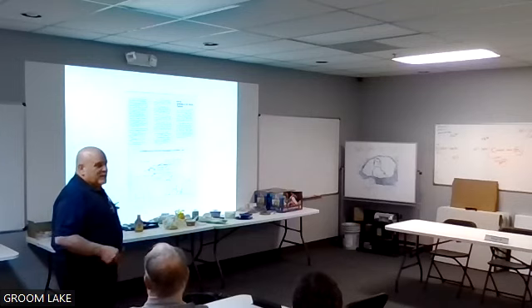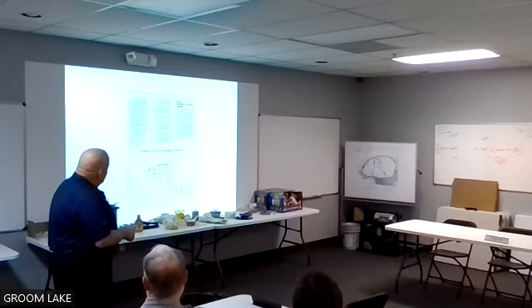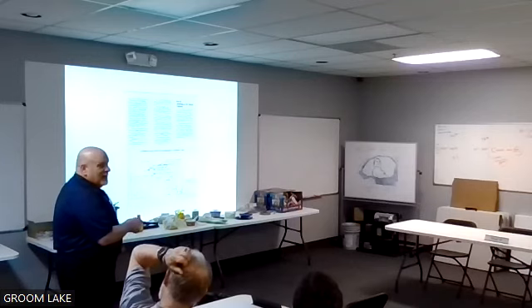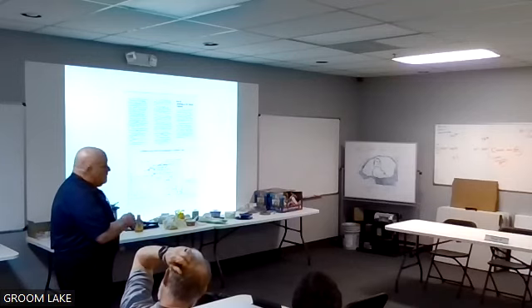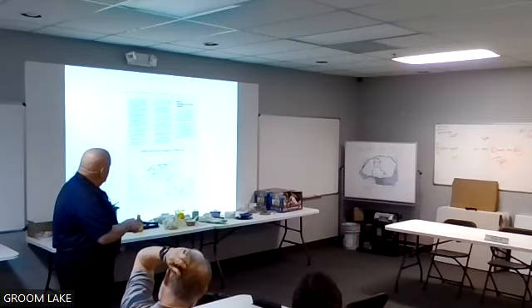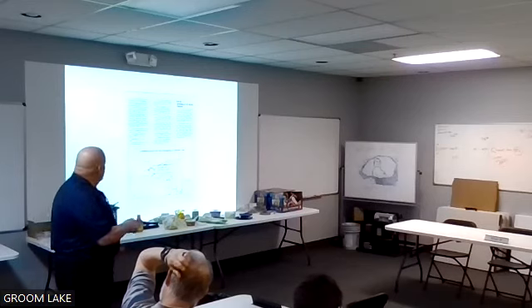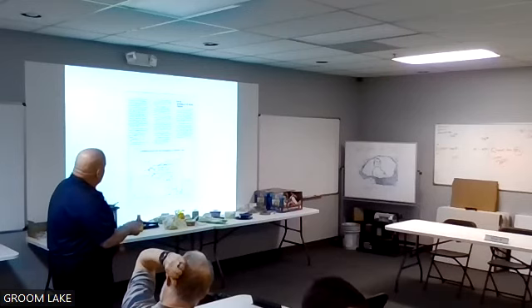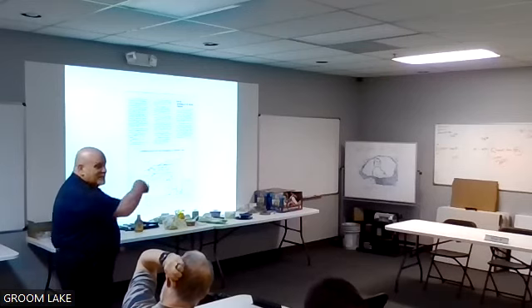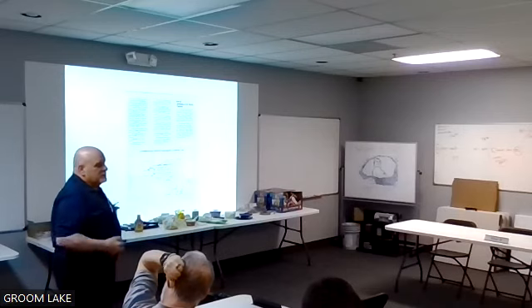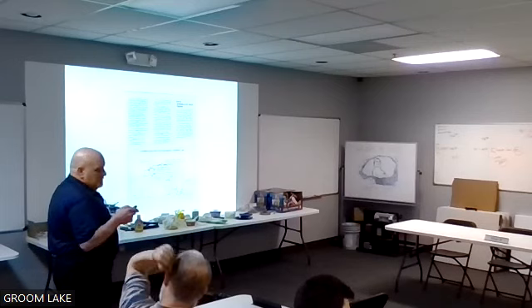You're taking up expansion space, really. So you always put this here, you put an air vent up here on this one, instead of returning it to the tank, I want it to go to atmosphere. And I want one air vent right at the last 90, so you need two air vents. One on top of the tank and one at that last 90 before you break down into the tank, put an automatic air vent there. Okay?